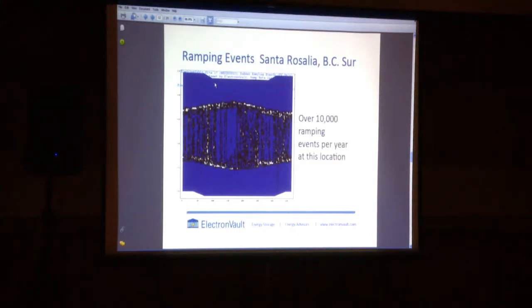This is for Santa Rosalia, across the border with our neighbors in Mexico. A similar large number of unplanned ramping events. This can cause frequency control loop problems. This can cause your grid frequency to wander rapidly and dramatically. And it can trip some of your control and safety systems off. So it can actually trigger blackouts if it shuts down a diesel genset.